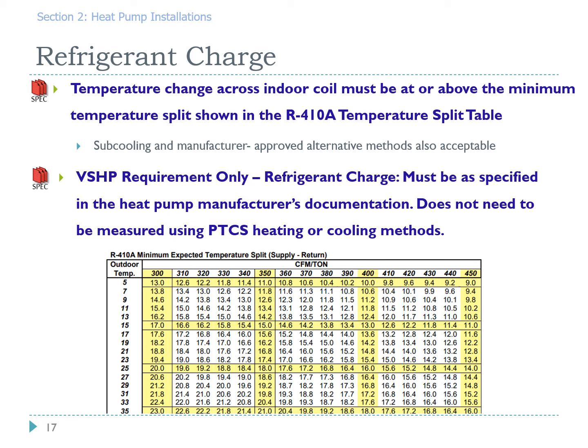Now we'll cover the refrigerant charge specification. The specification says that during wintertime commissioning, we need to use the temperature split chart shown at the bottom of the page. The chart inputs are airflow in CFM per ton that has already been measured, and the outdoor temperature to determine the temperature split. The temperature split on the table is a minimum temperature split that is measured across the indoor coil. This way we ensure that the refrigerant charge is correct.